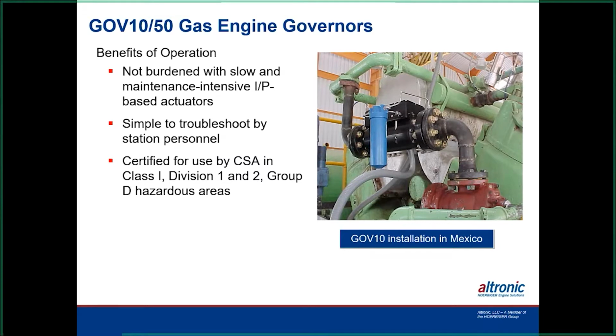Hey, Michael. Yes. Could you kind of explain to them why we had to have that zero pressure and that bleed off on that valve? Well, it's got the newer version on it there. It's got a self calibration on it. So when it gets ready to start, it's looking for zero pressure on the supply gas and on the manifold gas, so it can zero the transducers inside of it.